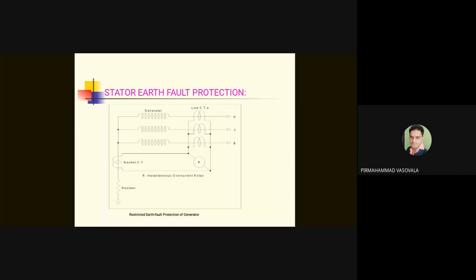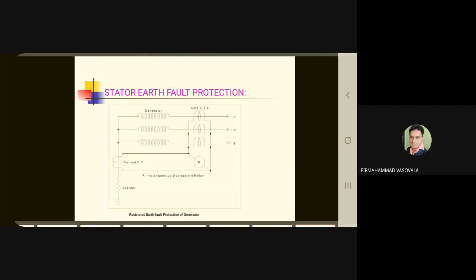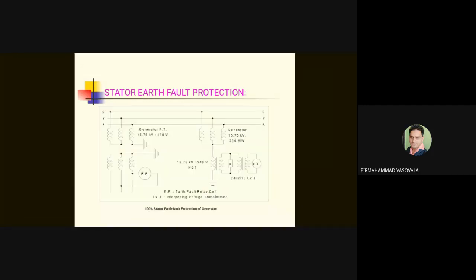So what should be used is such a kind of stator earth fault protection, which is based on third harmonic voltage, zero sequence voltage, and that gives rise to 100% sensitive stator earth fault protection.